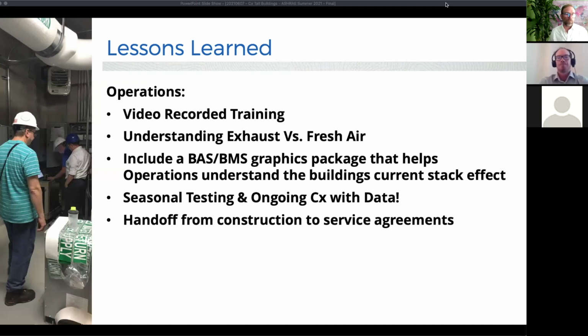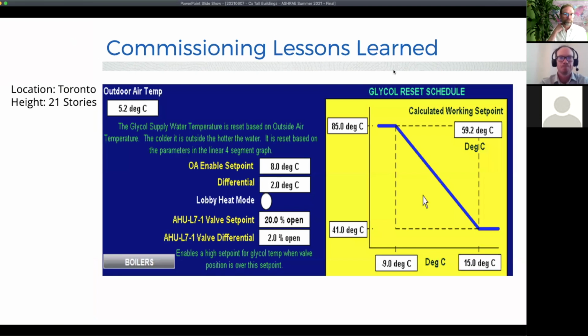We find that one technician will write a sequence completely differently than another technician, and a lot of times you get garbage in there. You get dead points. You get a lot of things that we spend a lot of time in the commissioning trying to figure out and reverse engineer. So that finishing line to the service agreement side is very, very critical.